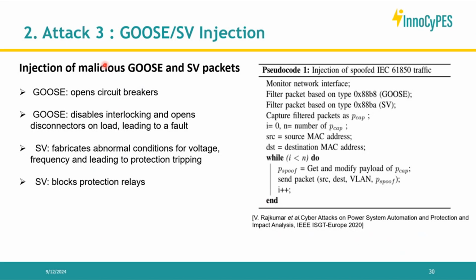With the same analogy, the purpose of a GOOSE or sample value injection is to inject a packet to simulate a fault happening on the grid when actually nothing is happening. So you would force the opening of a circuit breaker at the wrong time, or fabricate abnormal conditions like sample value voltage and current measurements. You can replay them, and the IED would then think there is a problem when actually nothing is happening - it's just a malicious actor that wants to compromise something on the grid.